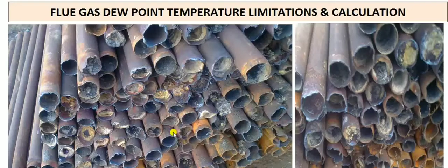Flue gas dew point temperature is a very critical parameter in the boiler or furnace operation. What is the dew point? Dew point is nothing but the temperature at which the first droplets appear. Actually, the gas will be in the gaseous, vapor state. So the temperature at which it gets droplets is called the dew point.